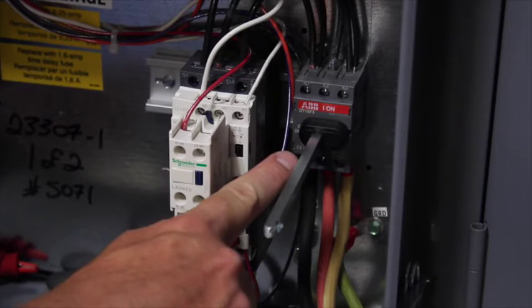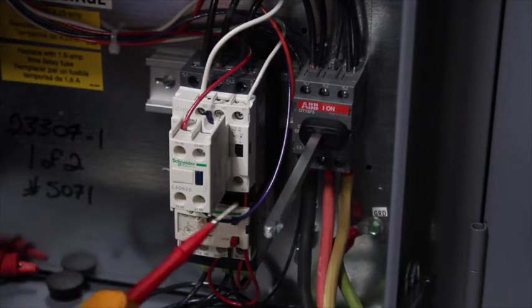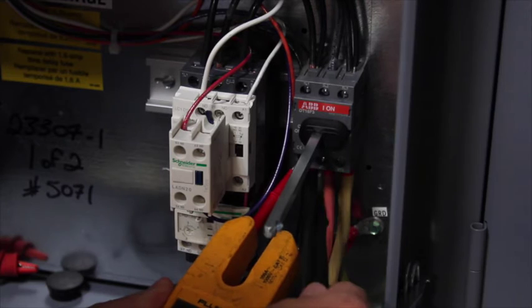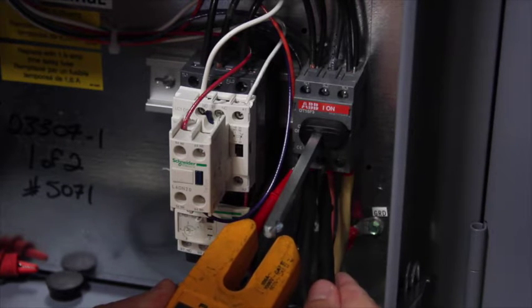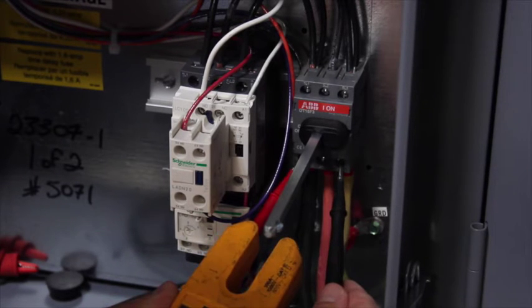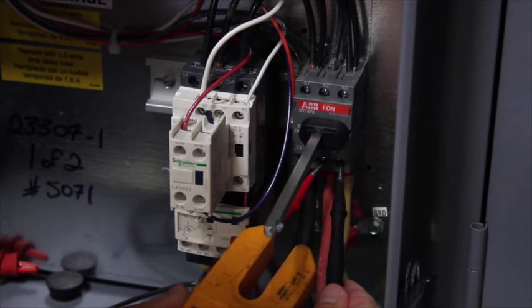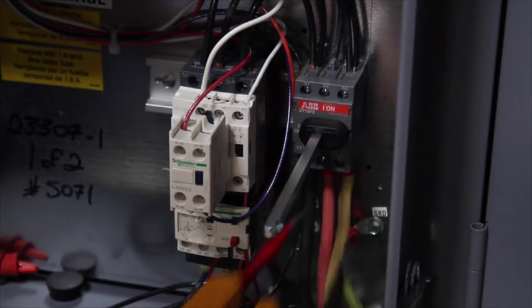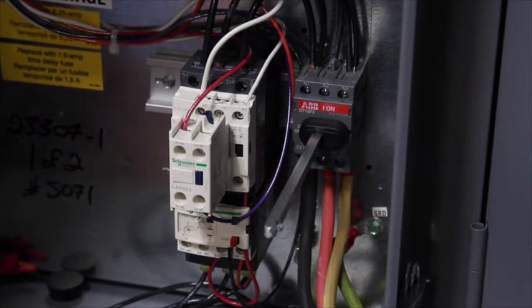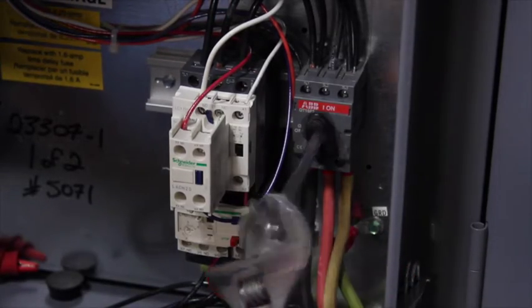Now verify the disconnect is in the off position. Using a voltmeter, check across all three legs of the supply power: L1L2, L1L3, L2L3. After you verify the voltage, turn the disconnect switch to the on position.